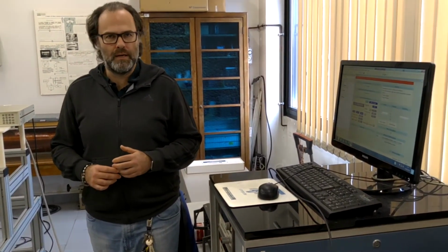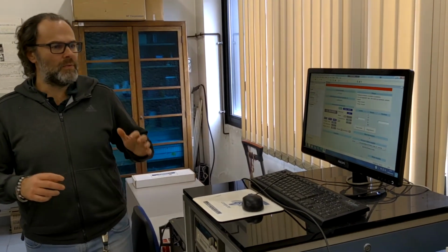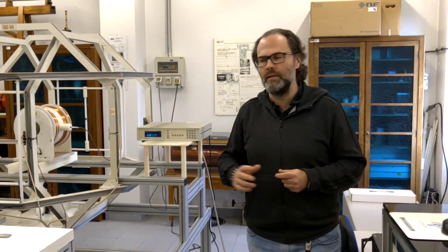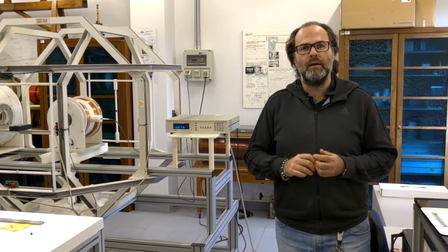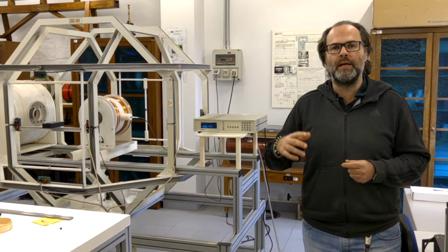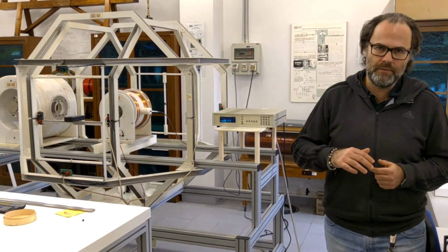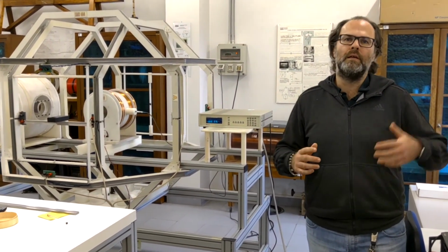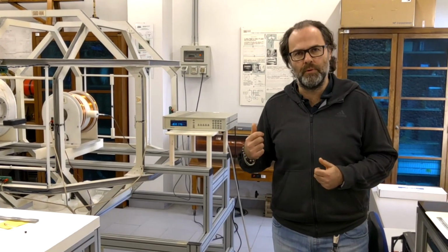To proceed with the calibration of the probe, we have a software that we have developed in-house that automates several tasks. The calibration is done by comparing the reading of the unknown probe to the field values that we know through the calibration constant of the coils that are there. We set different values of applied magnetic field, both positive and negative, and we do the comparison between the reference value and the value measured by the probe.